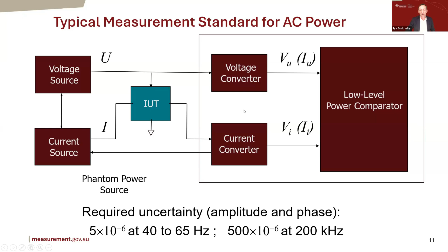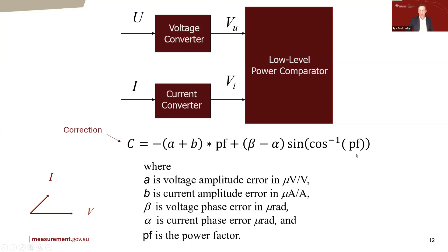One last bit of introduction with the formulas: the correction for the standard is a combination of amplitude and phase correction in the voltage and current circuit, and the combined correction depends on the power factor. So if it's a totally active load test point, the phase shift does not come into the correction, only amplitude errors do, and vice versa. At 90 degrees, the amplitude errors don't matter, and this formula shows it.